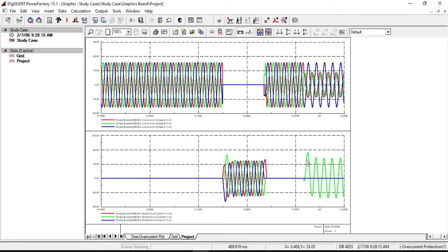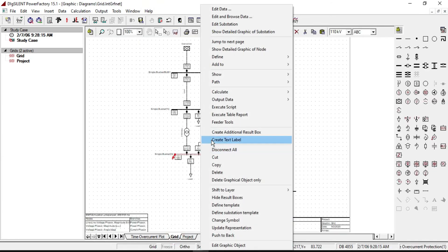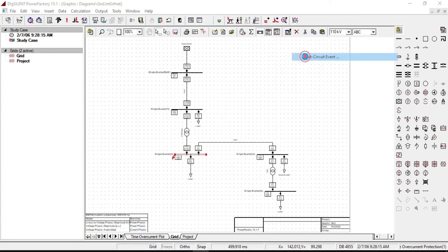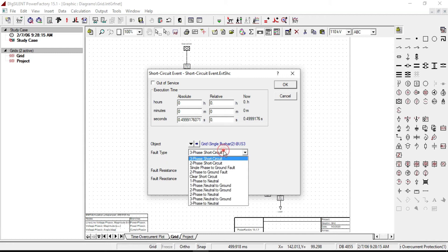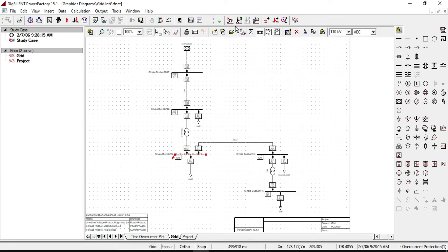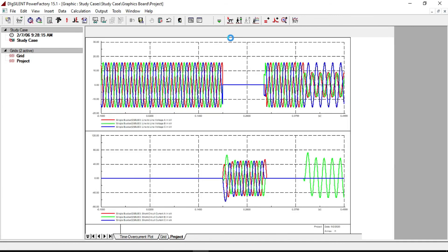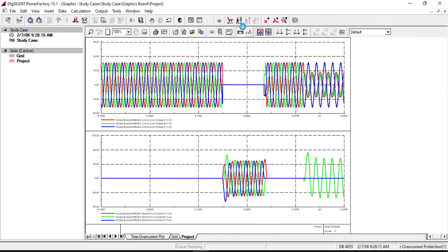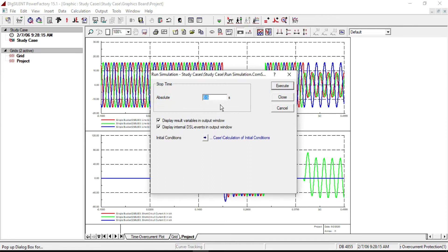Let's clear the fault after 0.5 seconds. We need to define another event — right click, from Define select Short Circuit Event. Change fault type to Clear Short Circuit and set the time to 0.5 seconds. Click OK. Since the fault clearing time for the single line to ground fault was 0.5 seconds, we need to increase the simulation running time. Let's set it to 0.8 seconds.